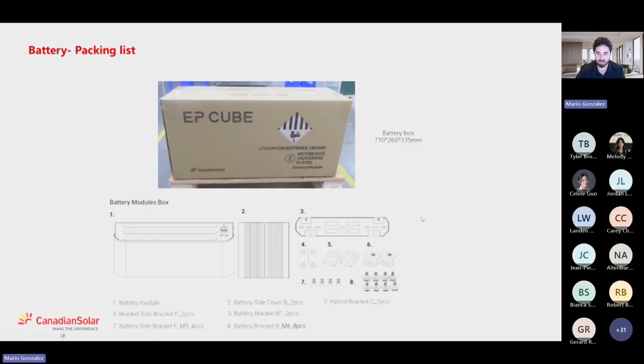And the base, of course, is the simpler one, with side covers as well. It's very important, you need it for every installation. Believe it or not, we've had installers try to install without the base. The main reason it's needed is that it terminates the DC circuit of the batteries. If you don't have the base, the batteries are in an open circuit, and there's no voltage or current flowing through it.